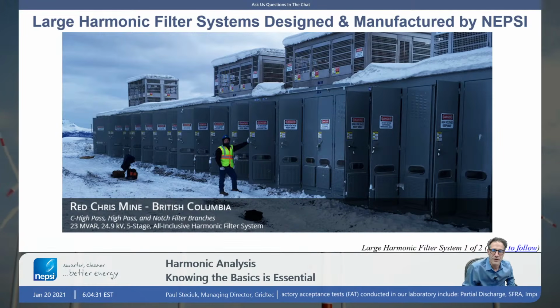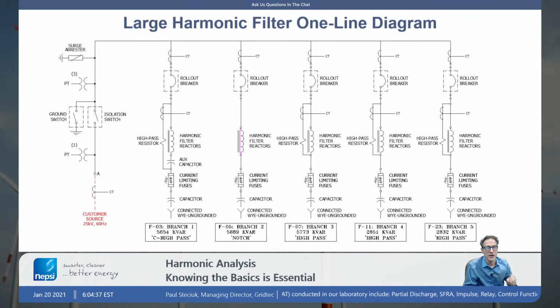So this is an example of a metal enclosed system. It's a metal enclosed harmonic filter system. It's a multi-stage harmonic filter system. When you peer into that system, what you see is all switching, all protection, all control. And this is the advantage of the metal enclosed system, is that it contains all switching, protection, control. It's in a compact, fully integrated solution. It's easy to purchase, it's easy to install, it's easy to commission.